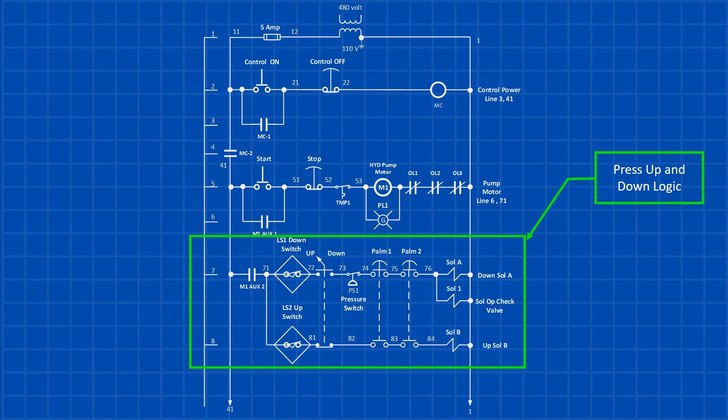Let's break down the press up and down logic. First, auxiliary contact 2 for the pump motor must be closed, meaning the pump is running for any movement to occur. For the press to move down, the press down switch must be inactive, as indicated by the normally closed press down proximity switch. Additionally, the up-down selector switch needs to be in the down position, and the press should not have reached the high pressure limit, which is monitored by a normally closed pressure switch.